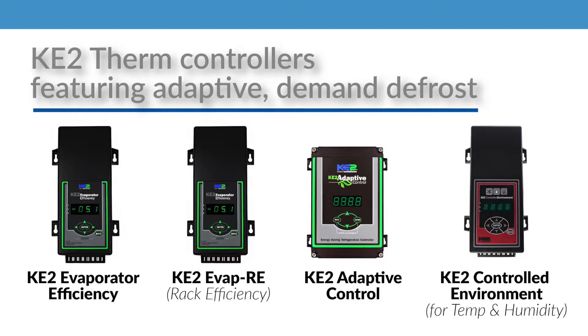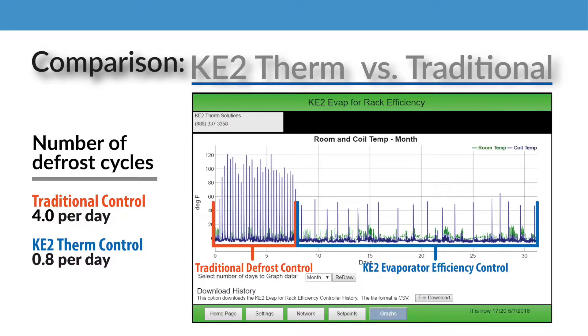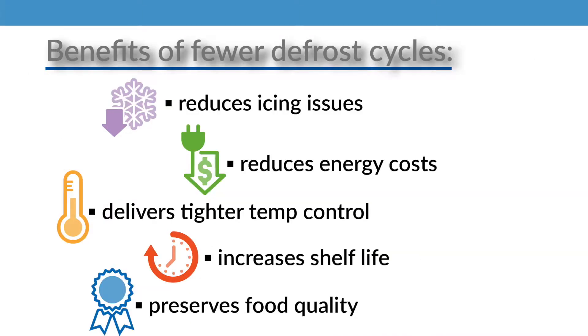So, let's take a couple of minutes to see how KE2 Therm's adaptive demand defrost controllers alleviate these issues and provide additional benefits. As you may know, all refrigeration systems require defrost cycles to remove accumulated frost from the evaporator. Traditionally, this was done on a schedule four or five times a day, whether the evaporator needed it or not. KE2 Therm takes a different approach — the KE2 Evap is smart enough to know when defrost is actually necessary and adapt in real time. This typically decreases defrost cycles from four or five times a day to once a day or less. It not only reduces the icing issues we mentioned earlier, it reduces energy costs and delivers tighter temperature control, as well as increasing shelf life and preserving the quality of stored food.